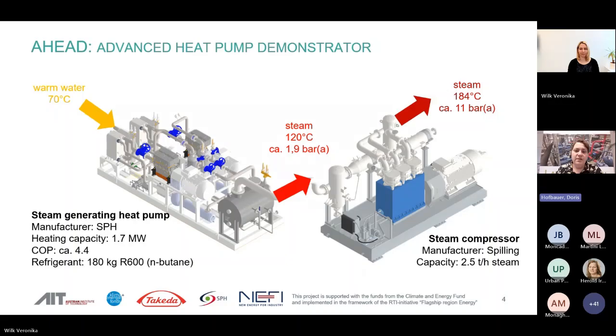The second part is the steam compressor, which is provided by Spilling, and which lifts the steam pressure and the steam temperature up to 184 degrees and 11 bar absolute pressure. The system then feeds into our production site and provides around about 2.5 tons of steam per hour into our network, and that's just from waste heat because we use heat pumps for the whole system. Veronica will now tell you more about the modeling and the scalability of the developed system.